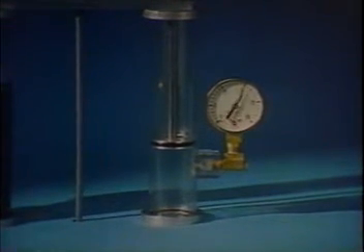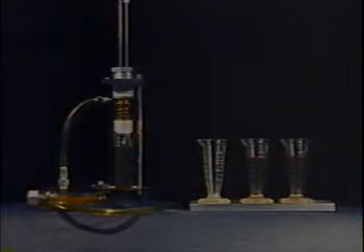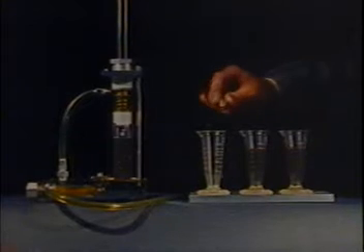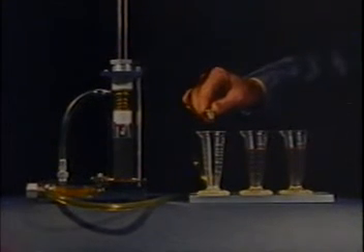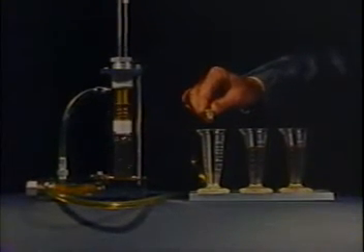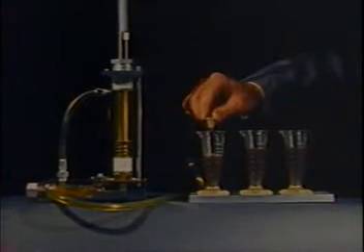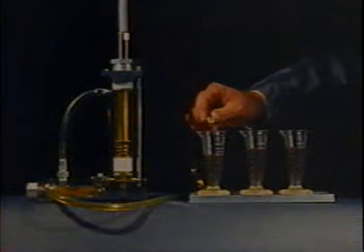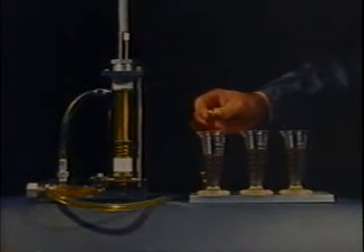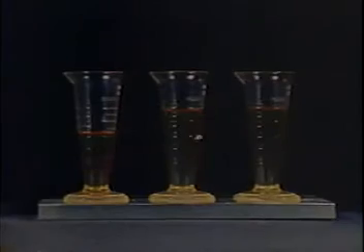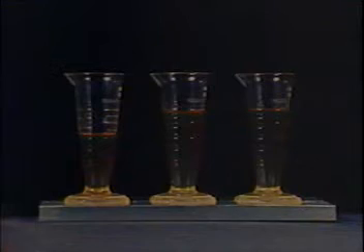This cushioning, spring-like effect of air, if trapped below the piston, would tend to interrupt constant flow and reduce the displacement of the proportioning pump by allowing some downward motion of the piston before liquid flow begins. Entrapped air must be compressed until pressure in the lower chamber equals the high pressure holding the discharge ball valve closed from above before outward flow can begin.